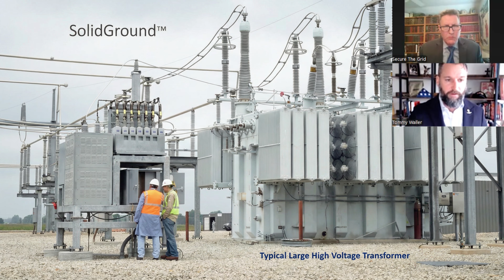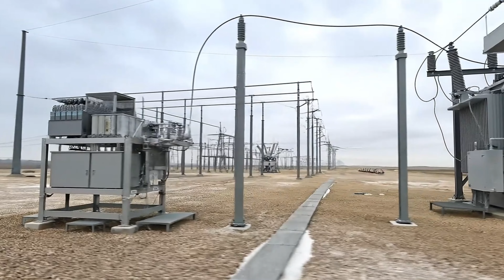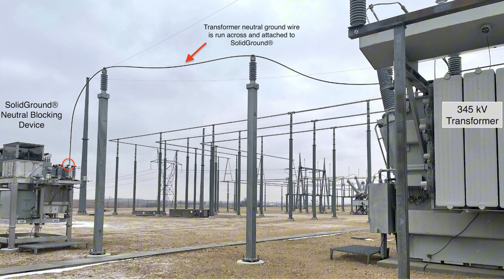On the left, you see it's called SolidGround—it's a neutral blocking device. And you see on the right the transformer. It may be difficult to see above these men, there's a wire up there that just connects to the neutral ground wire on that transformer. And it will sense that ground induced current and mitigate it—it will block it immediately.